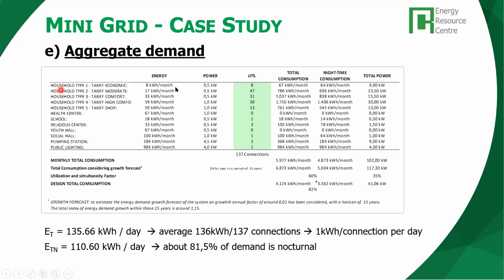In the end, we sum up all the different consumptions for all the types of customers we expect, 137. You see the total consumption from each type of customer, okay? In the end, we have a gross consumption expected in year one of roughly 6,000 kilowatt hour per month, with a night fraction of almost 4,900 kilowatt hour per month, and a total gross aggregated power of 102 kilowatts. That is what our survey and estimation with our tables gave us.